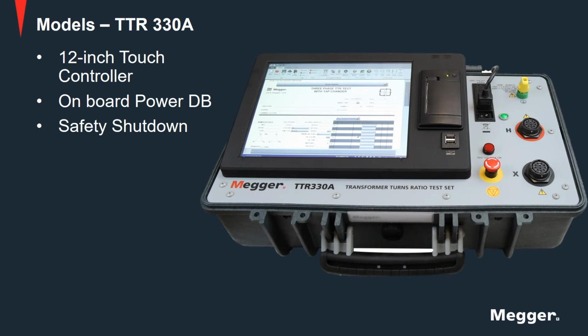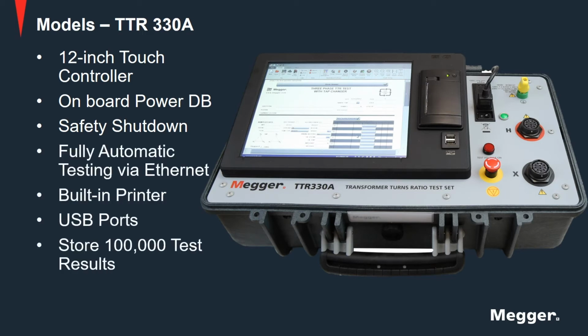Third is the TTR330A that has a 12-inch touch controller and onboard PowerDB. It also has the safety shutdown feature that protects against accidental shutdown of the instrument. This is achieved by safely turning off the Windows operating system together with PowerDB. This safe shutdown prevents damage to the internal memory and to the software operating system. It can be used for fully automatic testing via Ethernet. It also has a built-in printer, USB ports, and can store up to 100,000 test results.